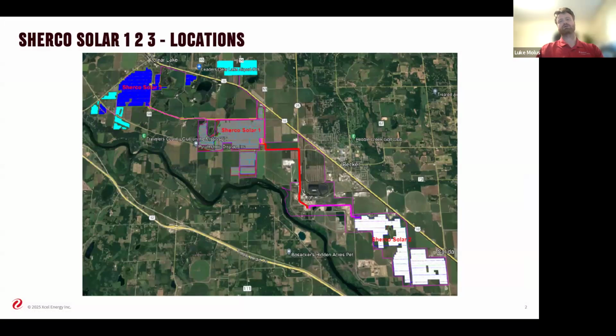When you're designing a large solar site like Sherco, you have your standard block design: 3 tiers of trackers, 1 inverter, roughly 18 LBDs per power block, which gets you a DC input to the inverter right around 4,800 kilowatts. The more same you can make the blocks, the better off you are, so you don't have to design different offshoots or different design blocks, and you can try to keep roughly the same amount of DC feed to your inverters. Trying to keep it all together is the best way to do it.